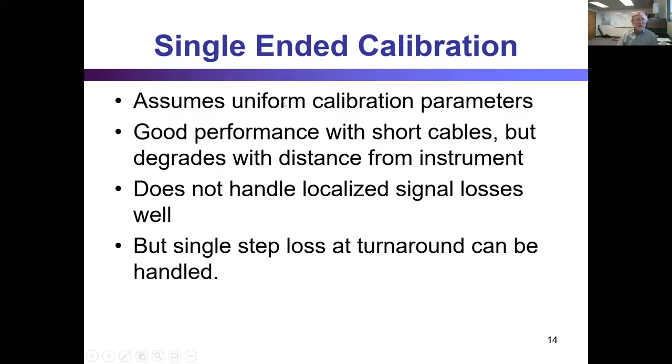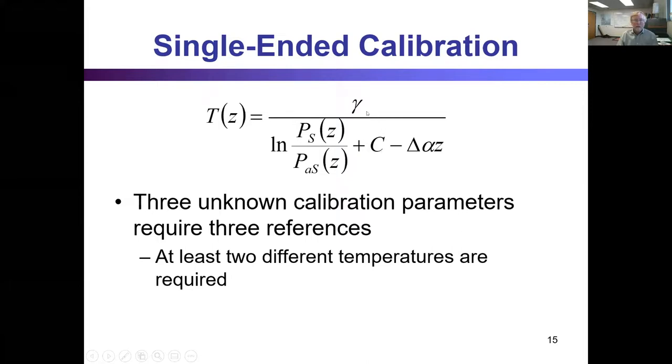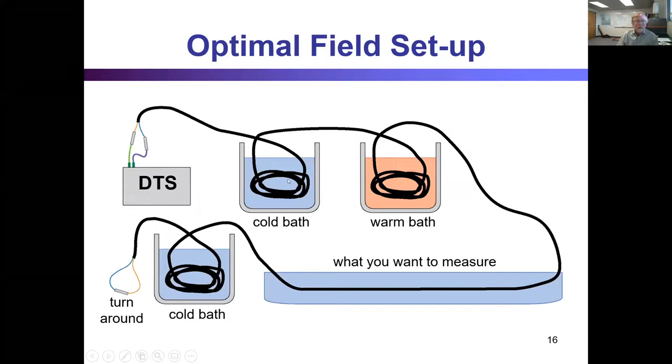The single-ended calibration assumes uniform calibration parameters in space. We can do a calibration every time we take a measurement, so it's not constant and uniform in time, but in space. It's good for short cables where we don't have much step losses. It can't handle these step losses well—we can handle one or two. And again, three unknowns—gamma, C, and delta alpha—requires at least three reference temperatures, and two of them need to be different, at least. Otherwise you can't invert the matrix. So here's commonly what we would do. We'd have a DTS, we'd put our cable through a cold bath, a warm bath—this is a duplexed measurement. We'd go out to what we're measuring, and if we're lucky enough, put some cable out in another cold bath or a warm bath someplace out in the field. And when I say some, you typically want to have at least 10 or 20 DTS measurement points in your calibration bath. So if your instrument is returning a signal every one meter, you want to have 10 meters, 20 meters in these baths.